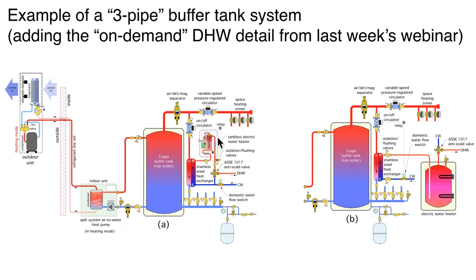Over here on the right, same basic idea — the only thing that's changed is I'm using a tank-type electric water heater as our final temperature boost. Assuming we have a heat pump, we might only be maintaining the buffer based on outdoor reset control. So we're only going to get a preheating effect through our stainless steel heat exchanger and will need something to top it off. Either of these is an option with a heat pump. If it were a ModCon boiler, you could probably eliminate the electric tank and simply make sure the buffer tank is warm enough to provide 100% of your domestic hot water.